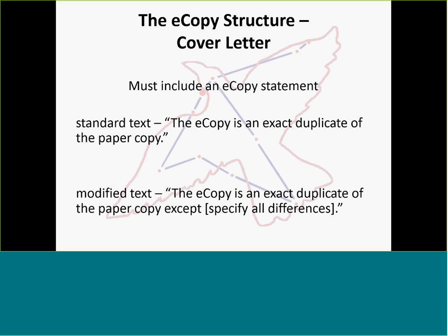So, your cover letter. eCopy must have a cover letter with the statement: The eCopy is an exact duplicate of the paper copy. And there is something different: you need to try to avoid this if at all possible, but if it's unavoidable because of the nature of the data, then you have the text, it's an exact duplicate of the paper copy except, and then you list out absolutely everything that's different.